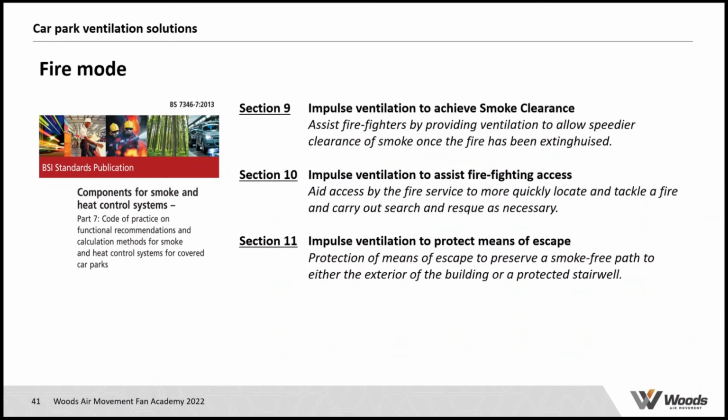So even though it's an engineered solution, a Section 10 system is not so much to allow people to evacuate from the car park. It is to assist firefighting access, making it more likely that the fire service will do an intervention from the inside.